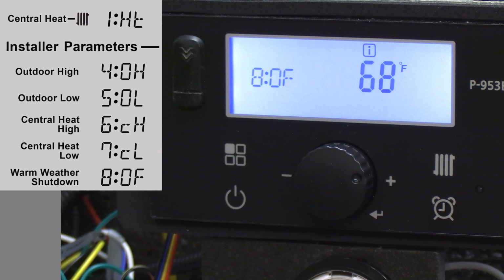Next is your warm weather shutdown. That's parameter 8, and that's defaulted for 68 degrees. So if you like that value, then just leave it there. Again, at 68 degrees or above, the heat will not come on. If you do have an indirect tank tied into your system, the boiler will still operate to provide heat to the domestic tank or indirect tank.